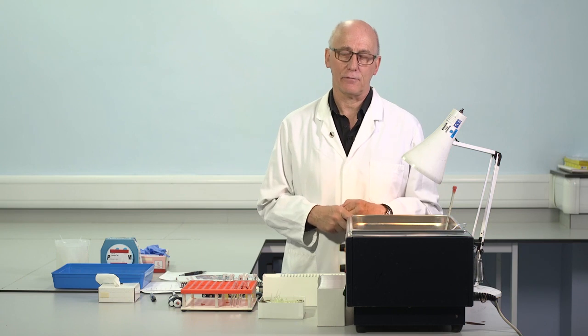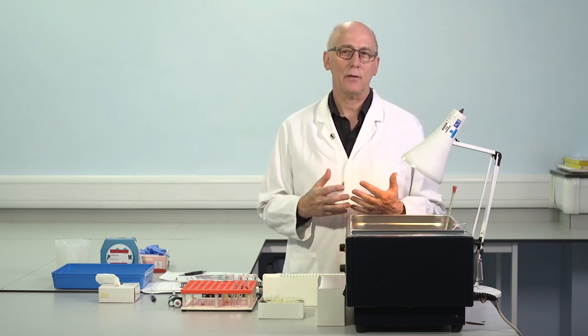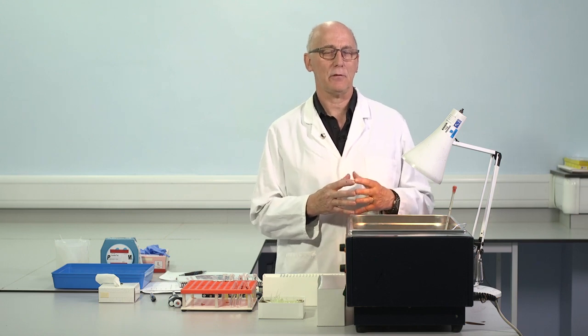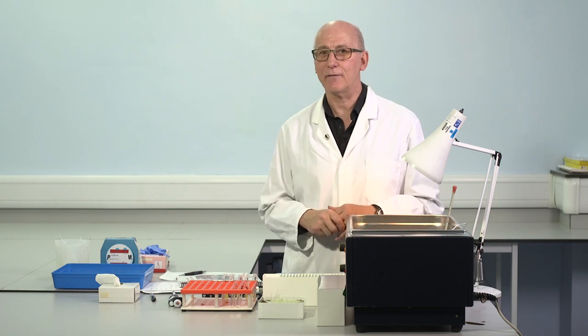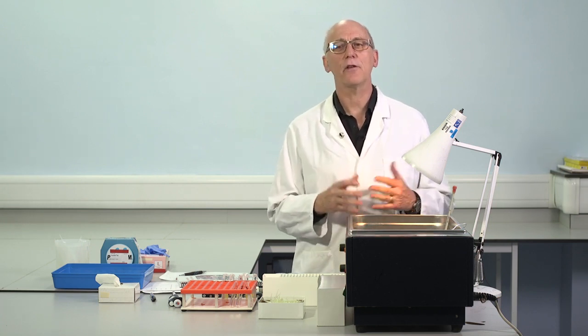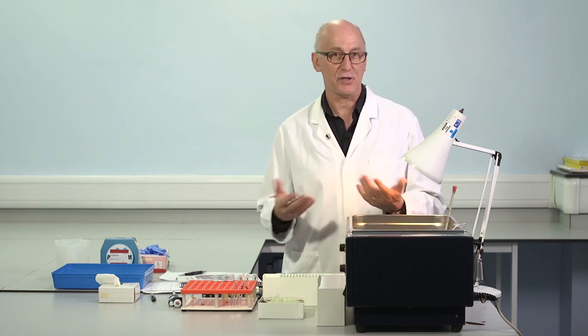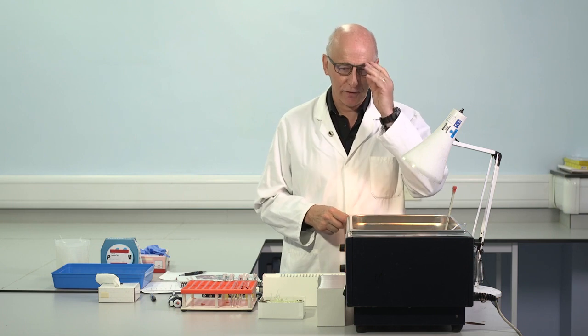An obvious one is cost, of course, but I think in addition to that, such a sample, because it's a patient material, it's closer in its properties to patient samples, and I'm sure that's an advantage, because it's difficult to keep control materials with the same properties when we have to go through freeze-drying lyophilization. So I think there are a number of advantages.